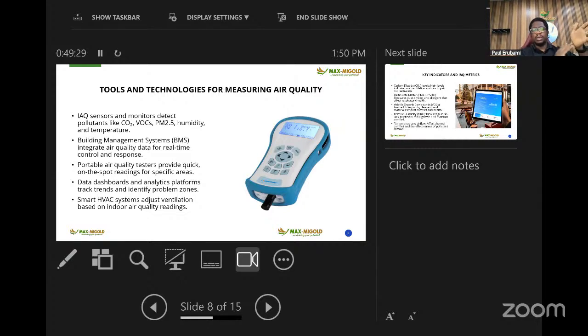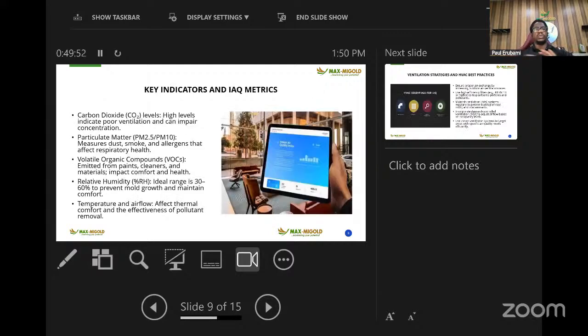There's a screen that you can just put on and it reads the air around and gives you a reading. So if you don't have an automatic system for bringing in fresh air, once it reads that something is below a certain threshold, you just open windows and bring in fresh air. This is a practice that will improve the health and well-being of users of our facilities. So it's important that we monitor carbon dioxide, particulate matters, volatile organic compounds, relative humidity, temperature, and airflow as a minimum. These are key indicators of indoor air quality that you must monitor.